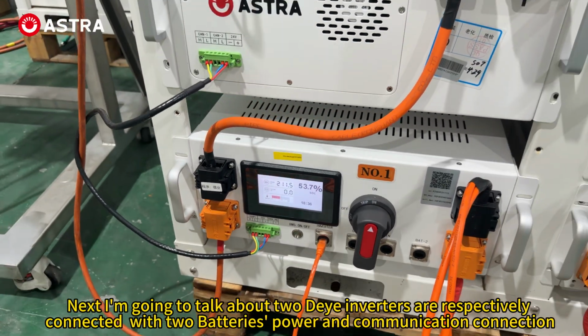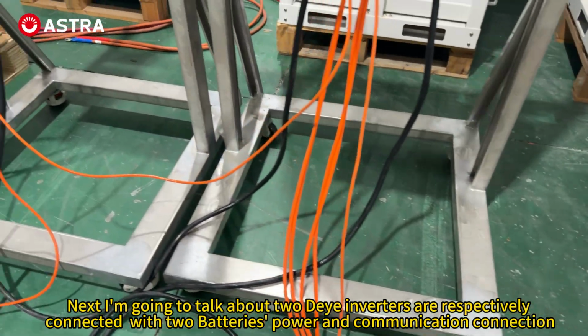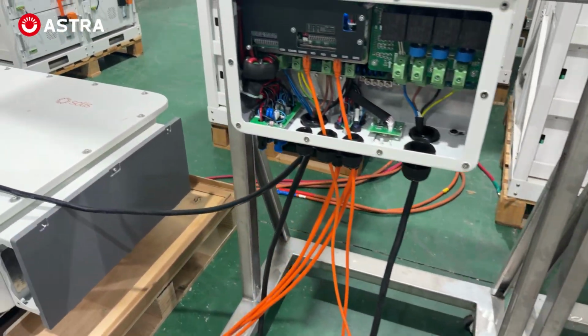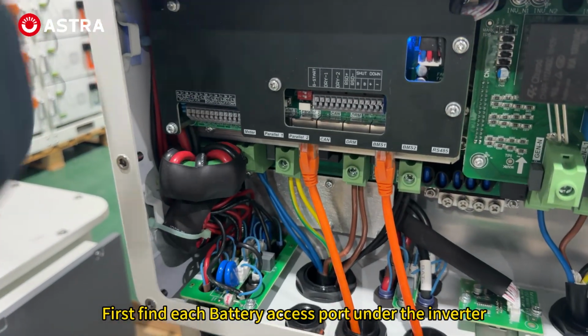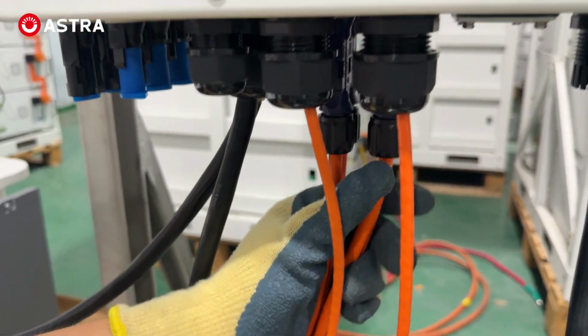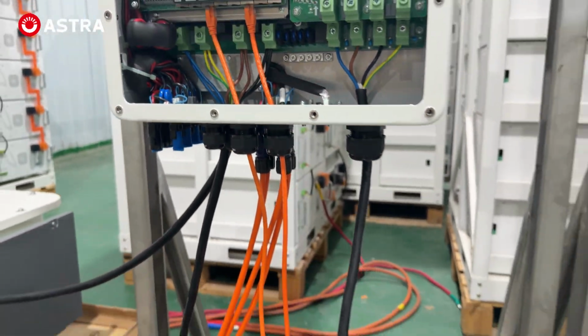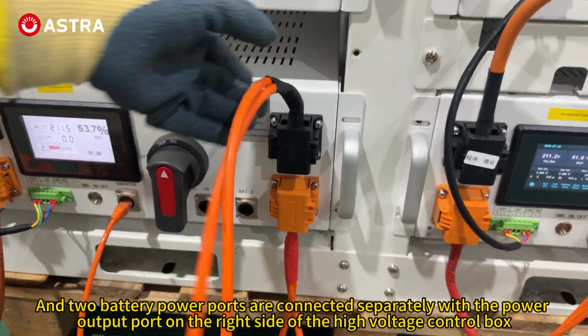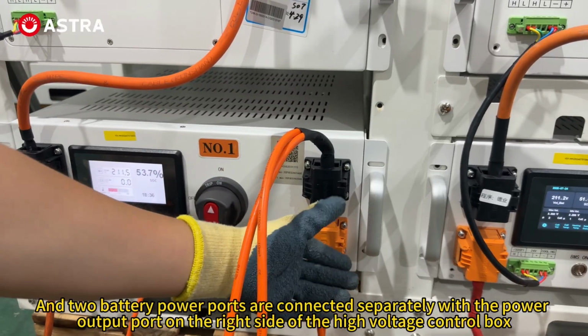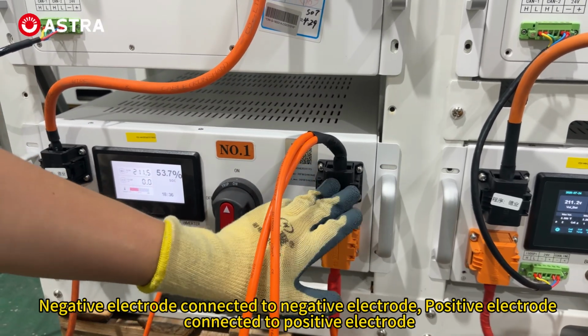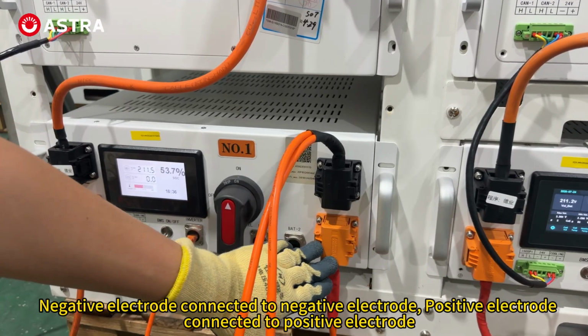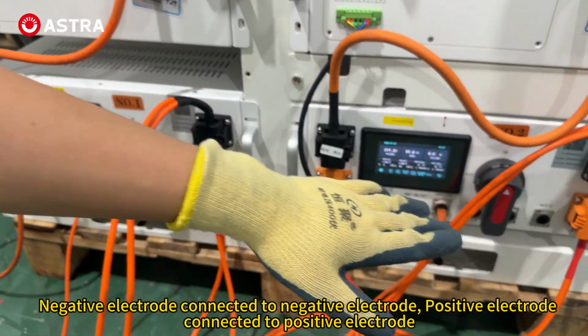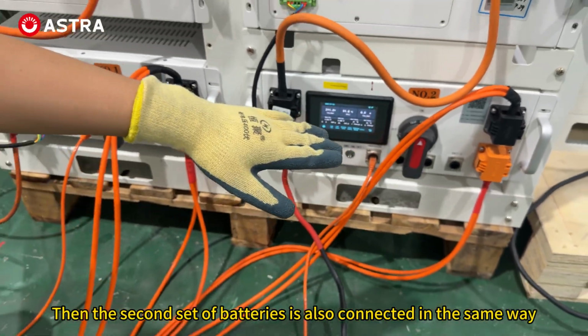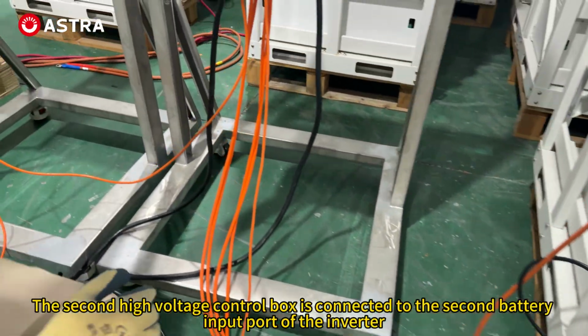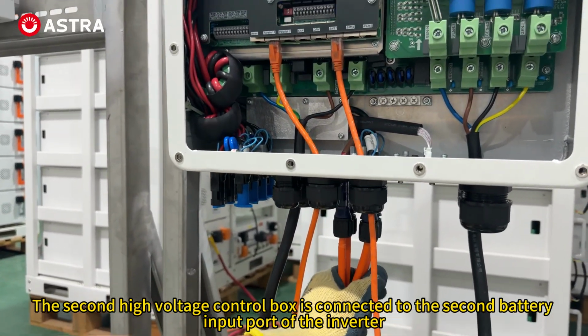Next, I'm going to talk about how the 2 inverters are respectively connected with the 2 batteries for power and communication. First, find each battery access port under the inverter. And the 2 battery power ports are connected separately with the power output port on the right side of the high voltage control box. Negative electrode connected to negative electrode, positive electrode connected to positive electrode. Then the second set of batteries is also connected in the same way. The second high voltage control box is connected to the second battery input port of the inverter.